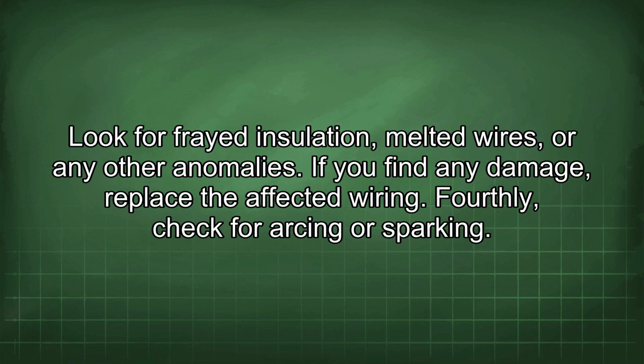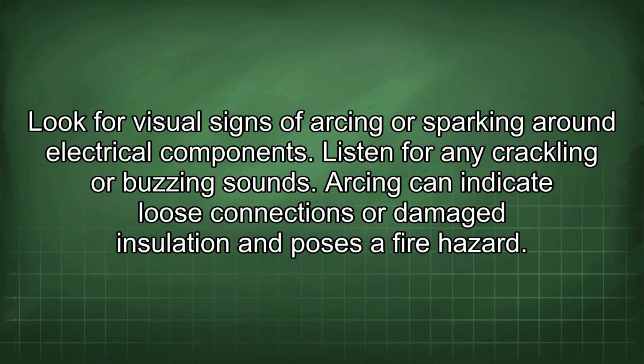Fourthly, check for arcing or sparking. Look for visual signs of arcing or sparking around electrical components. Listen for any crackling or buzzing sounds. Arcing can indicate loose connections or damaged insulation and poses a fire hazard.